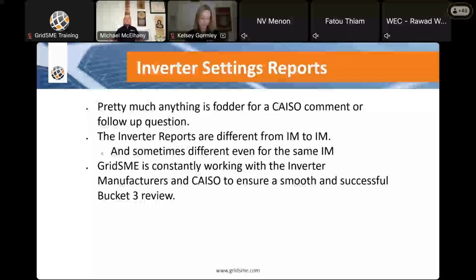final thing is pretty much anything is fodder for CAISO comment or follow-up question. We recently had one get kicked back because they needed to know the number of inverters per feeder collector. And we've never had that one before. There is a requirement to identify the number of inverters, but we've never had it at that level of granularity. So we're always playing catch up with their requirements. We do try to push back and ask where are you getting that requirement from, to make sure that we're not inventing new things that we have to follow. Because we've had things that were approved 2 years ago that aren't getting approved a year ago, stuff that was approved a year ago, 6 months ago that isn't getting approved today. So we're constantly working with them on that.